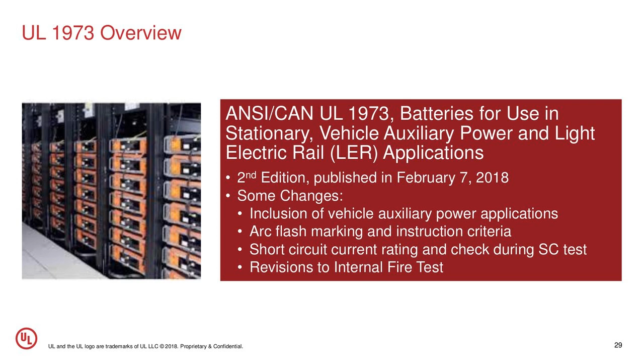We should have probably had that from the beginning, since it could apply to these battery systems, so we've added arc flash markings and instructions. We have a short circuit current rating that was important to the inverter industry. Anyone connecting to a battery system wants to know what that short circuit current is so they can see if their system can handle it, so we always do a short circuit test.